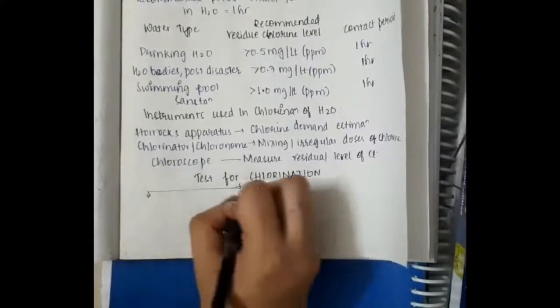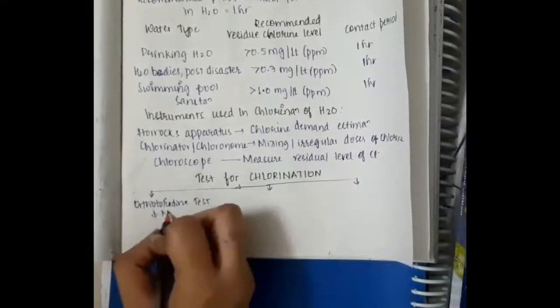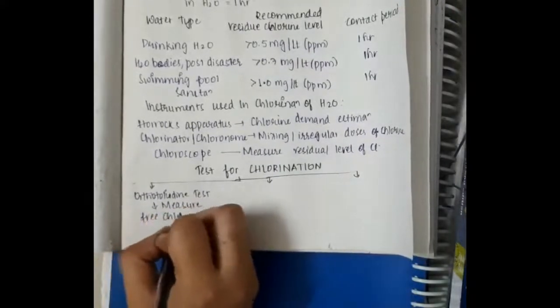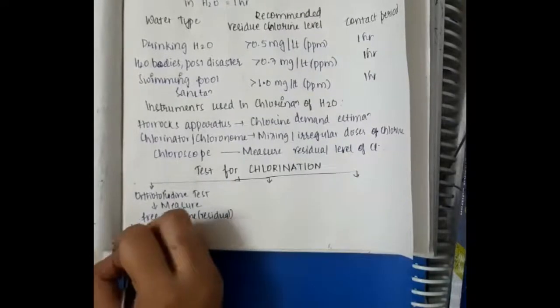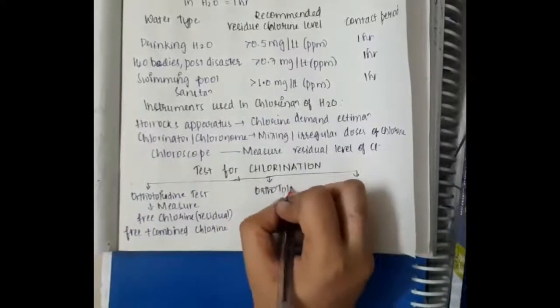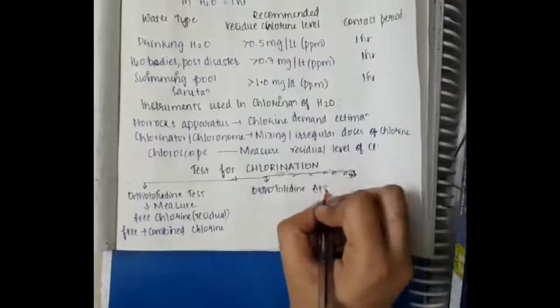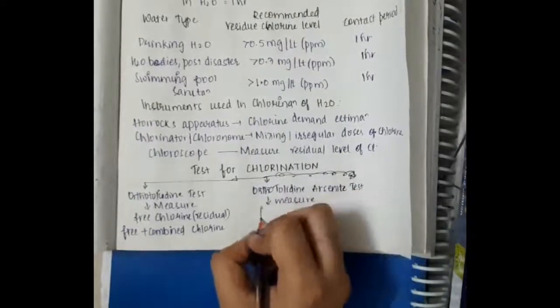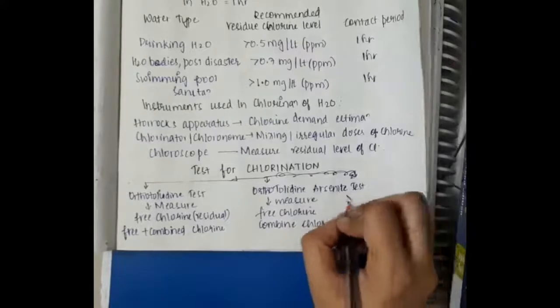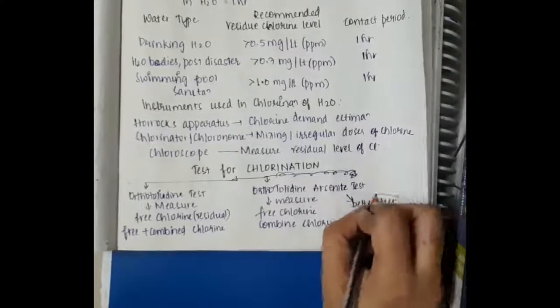Tests of chlorination are of three types. The first test is the orthotolidine test, which measures the free chlorine — that is residual chlorine level — and also the free plus combined chlorine levels. The second is the orthotolidine-arsenite test, which measures free chlorine and combined chlorine separately. It is a better test when compared to the orthotolidine test.